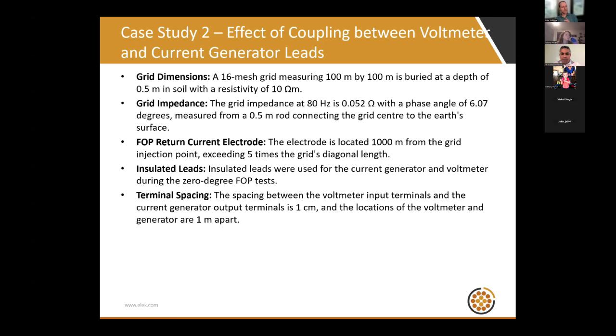So obviously, if those leads are nearer to one another, running in parallel but nearer, there'll be a higher degree of interference. So we can also simulate that. So we could say that perhaps we need to run in the same direction, our voltage measurements, but what should be the ideal or the recommended separation between those leads to minimize or reduce interference of the voltage measurements to an acceptable level?